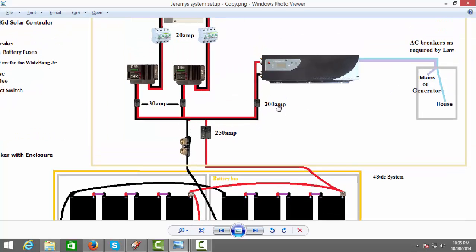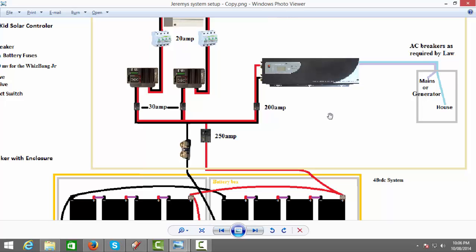As well as my inverter with a 200 amp fuse or should I say breaker, and also a 250 to my batteries. Now I'm also going to be wiring in a generator. So that's going to be run off a 15 amp socket and a fuse. And I'm going to have a changeover switch put in there as well, which is specially designed for generators. So if I want to go off grid I flip the switch to off which will kill the grid power. And then if I need to charge my batteries for some reason like not enough sun, I simply flick it into a zero mode, kick the generator over, and then hey presto I'm charging my batteries as well as running my house off the generator at the same time.